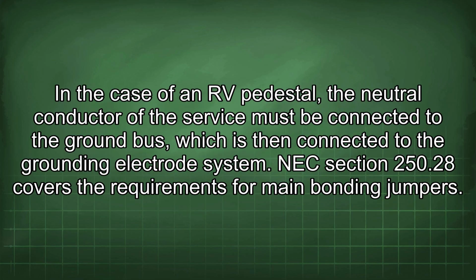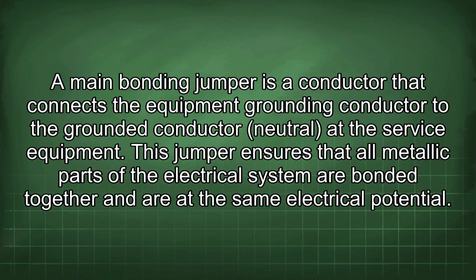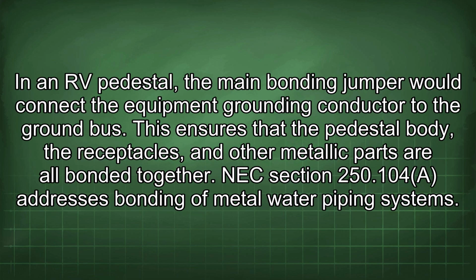In the case of an RV pedestal, the neutral conductor of the service must be connected to the ground bus, which is then connected to the grounding electrode system. NEC section 250.28 covers the requirements for main bonding jumpers. A main bonding jumper is a conductor that connects the equipment grounding conductor to the grounded conductor (neutral) at the service equipment. This jumper ensures that all metallic parts of the electrical system are bonded together and are at the same electrical potential. In an RV pedestal, the main bonding jumper would connect the equipment grounding conductor to the ground bus. This ensures that the pedestal body, the receptacles, and other metallic parts are all bonded together.